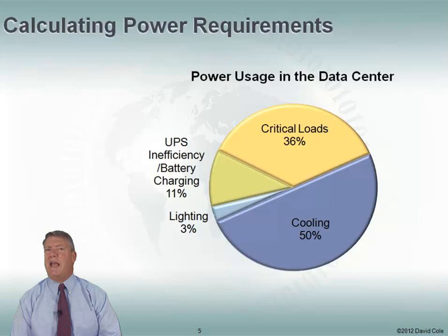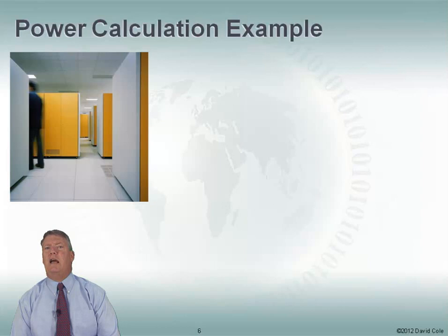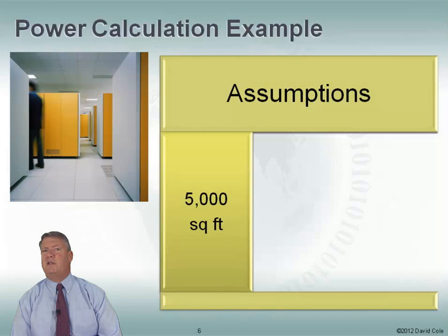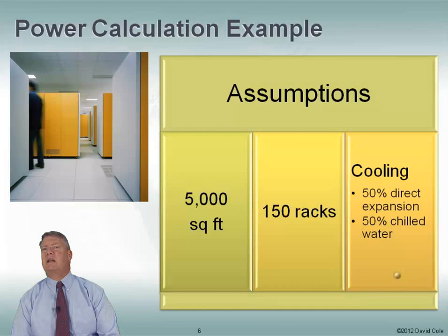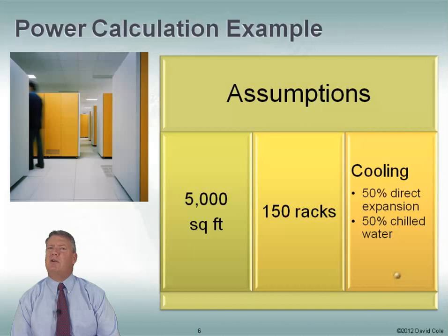Let's go through an example of what a typical data center design company would use to calculate your power. We have to start with some assumptions. Let's assume we're going to have a 5,000 square foot data center, put 150 racks in there, and half of our cooling is going to be direct expansion and half is going to be chilled water. There is a difference in costs for different types of cooling strategies.